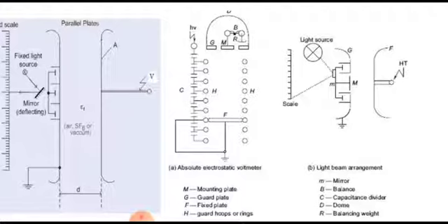Now in order to measure the given voltage with precision, the disc diameter is to be increased and the gap distance is to be made less. You have to increase the disc diameter and decrease the gap distance. The balancing weight gives the controlling torque.